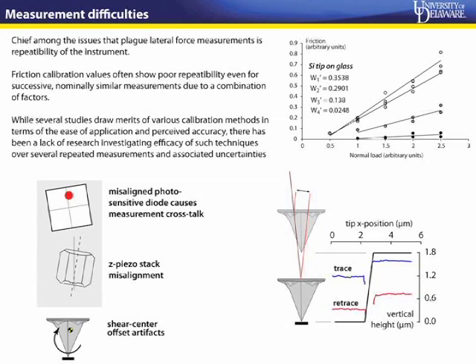Almost all the methods treat calibration as a separate step from the actual measurement. You calibrate an AFM cantilever in one step, and then you go down to making measurements with that calibration constant. So you can imagine if you have uncertainties like the position of the piezo, or even aside from that, if the cantilever chip is mounted differently, or if there is any change in the optical path length of the laser within the AFM, those calibration constants that you obtain during the calibration step may not necessarily be applicable or accurate for the actual friction measurements.